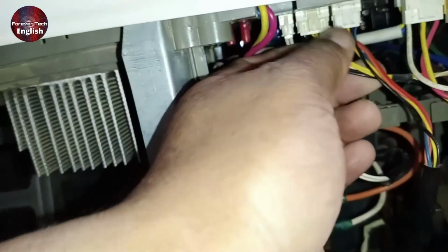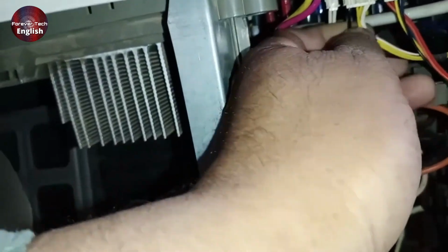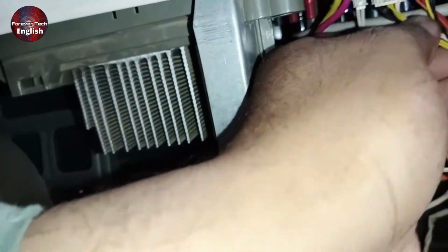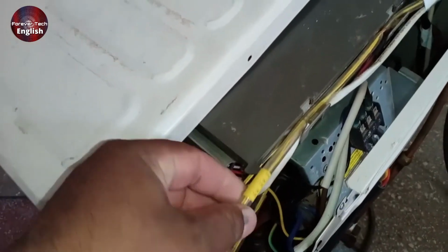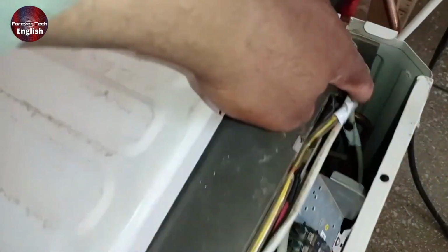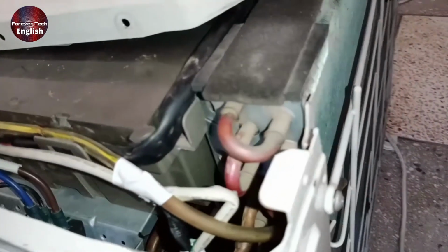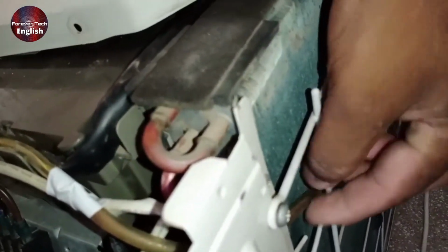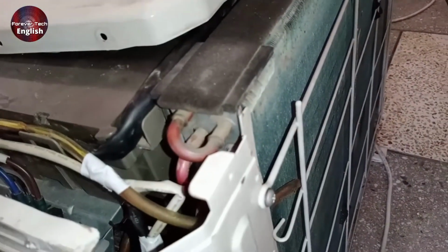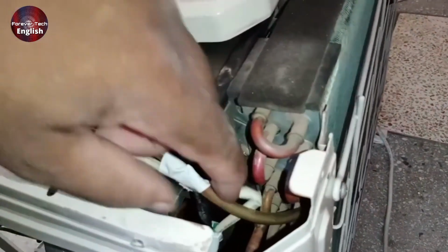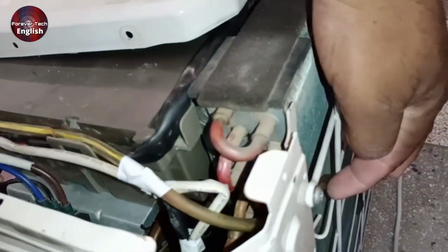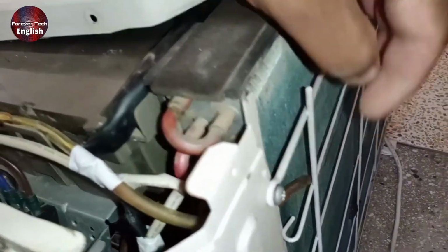Look, all three thermistors are installed in the same place, in the same connector, but the yellow wire here is the ambient temperature sensor. Now let me show you where this wire goes. As you can see, it runs from here to the back side of the outdoor unit. On the back side of the outdoor unit, it is installed openly, as you can see. This sensor is only sensing the outdoor temperature, so if it's hot, the unit can run according to the heat, and if it's cold, it can run according to the cold.